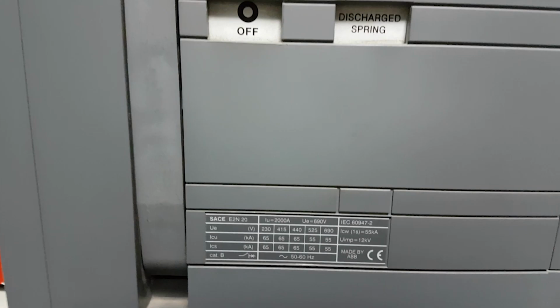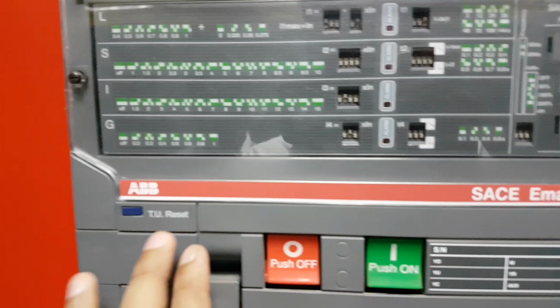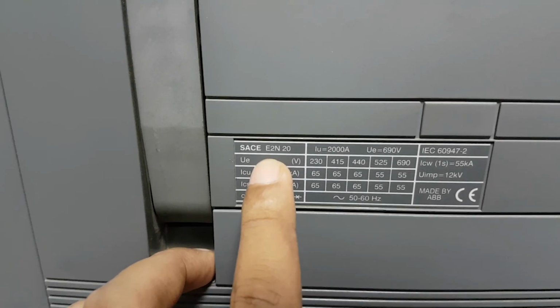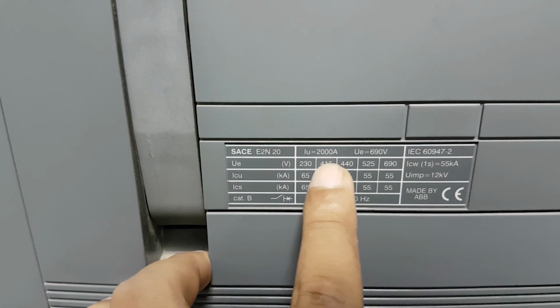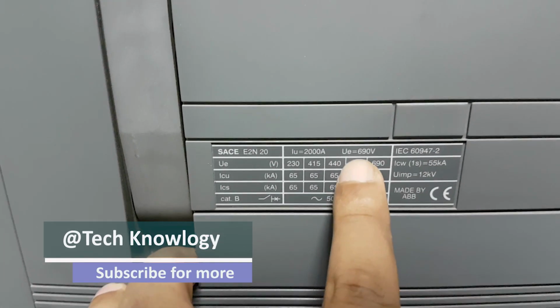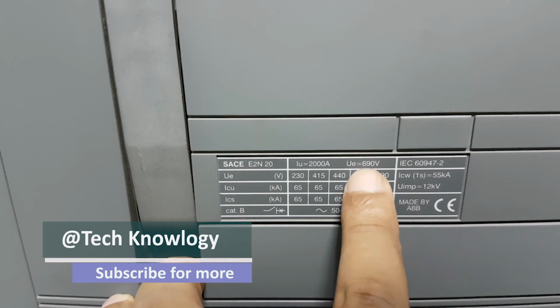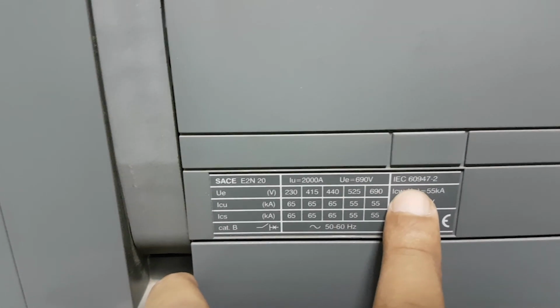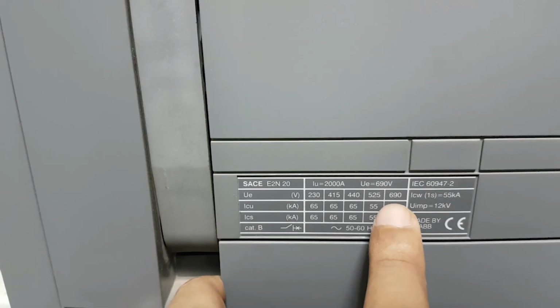Friends, this is an ACB of ABB make, an Emax ACB. You can see from here its nominal current is 2000 ampere and nominal voltage is 690 volt, IEC 60947-2.